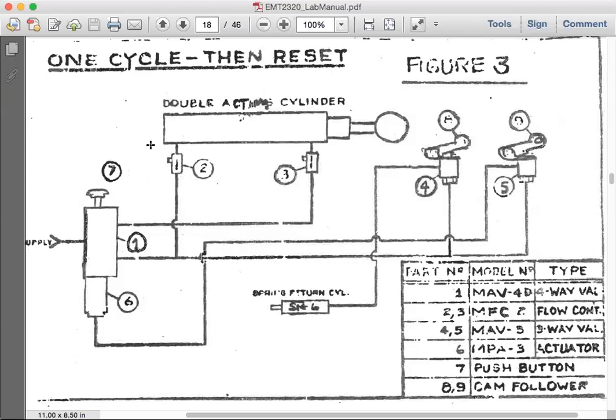If you had the arrow pointing up, then basically you would control the pressure entering the left chamber. Therefore, number 2 would start to control the extension by controlling the pressure. And if this number 3 would remain the same, then basically both 2 and 3 would control extension. 2 would control how quickly the pressure enters the left chamber, and 3, how quickly you depressurize the right chamber. So both of them would control extension. Then none of them would control the return of the piston.